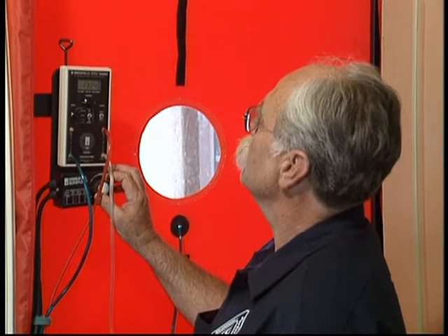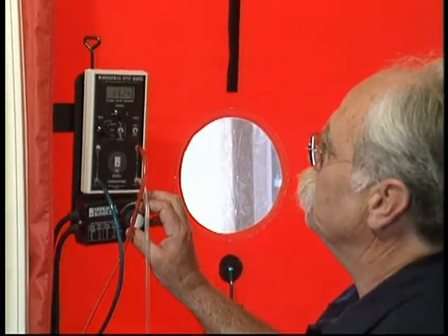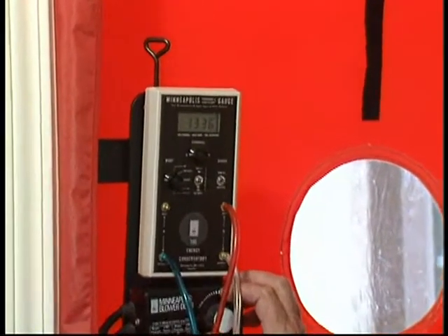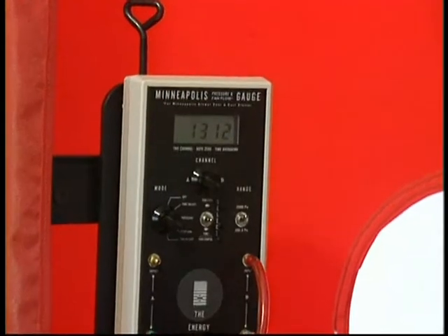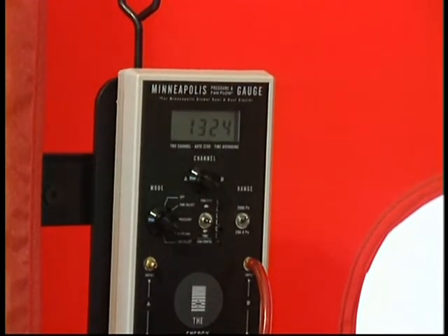Yes, sir. And what are the typical ranges in leakage that you find on California homes? Oh, I've got them as low as 400 and up to 9,000 cubic feet per minute, Steve. Really? Well, yeah, wide range. Now, what's typical for a 2,000 square foot house? Oh, around 1,500 to 2,500 cubic feet per minute. And we can test this house, right? Oh, yeah. In fact, let's do that.